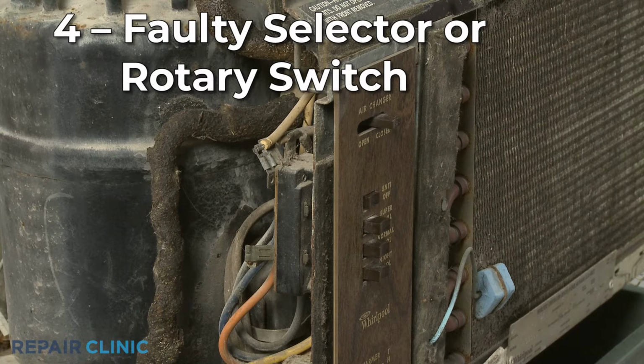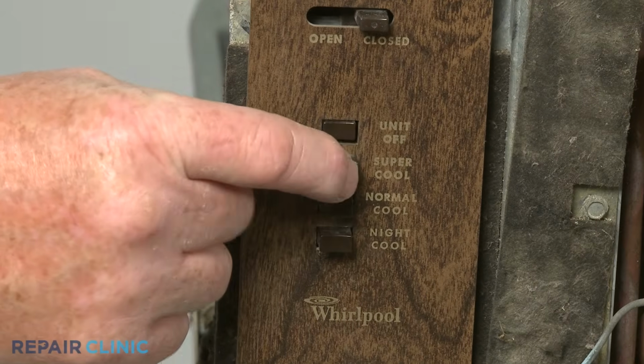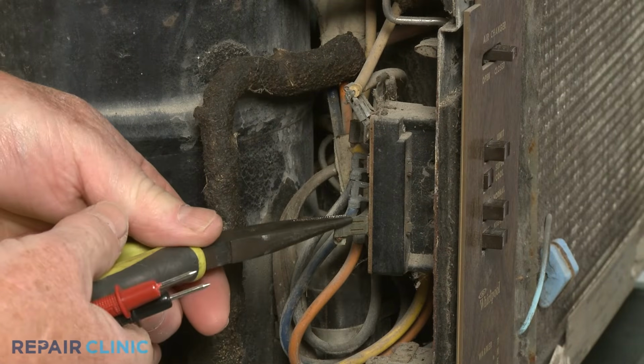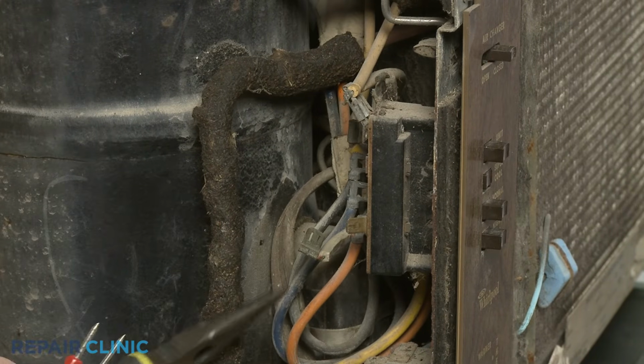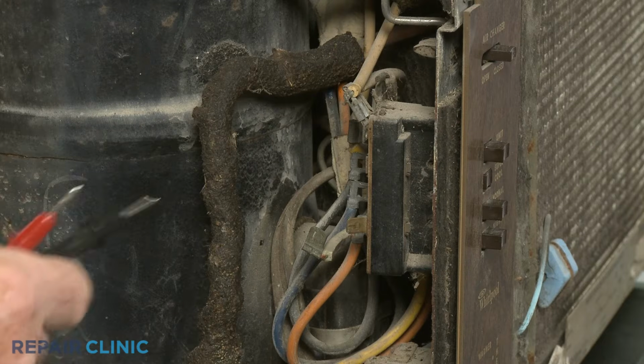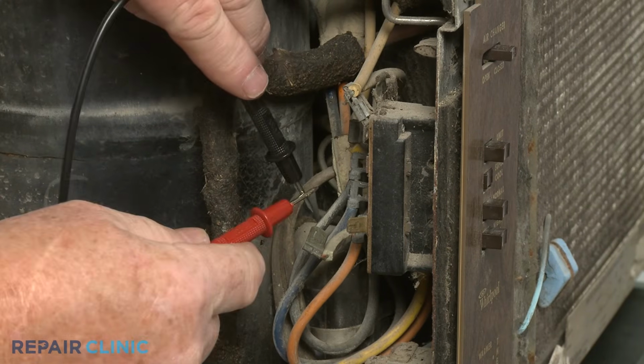A selector or rotary switch is used to activate the fan motor. If the switch is faulty, the fan may not work. On some units, you can set the switch for cooling and use a multimeter to test the switch for continuity. If the switch tests negative for continuity, the switch will need to be replaced.